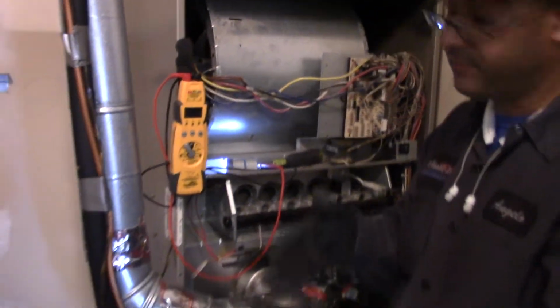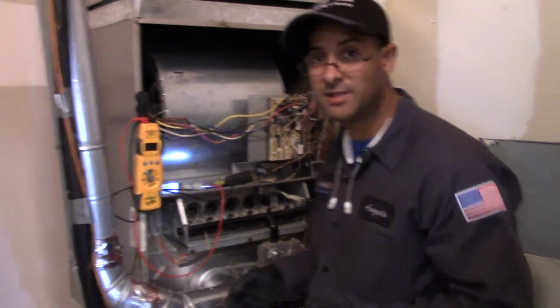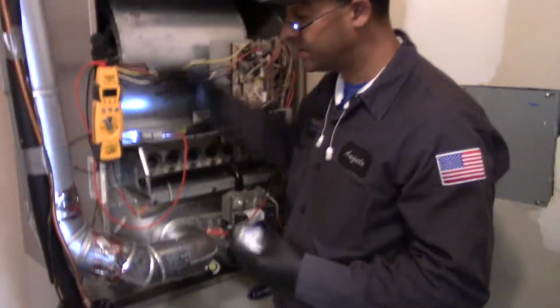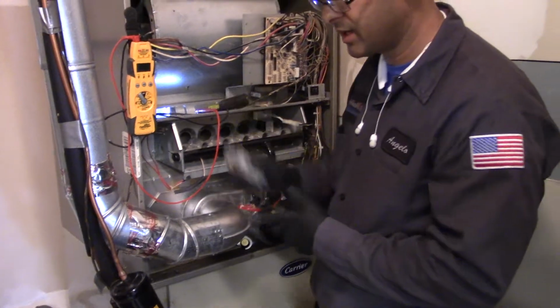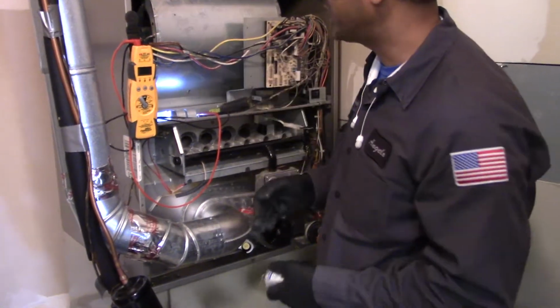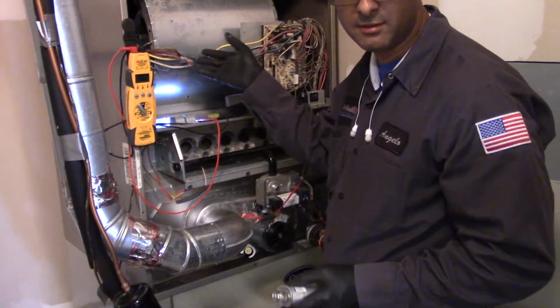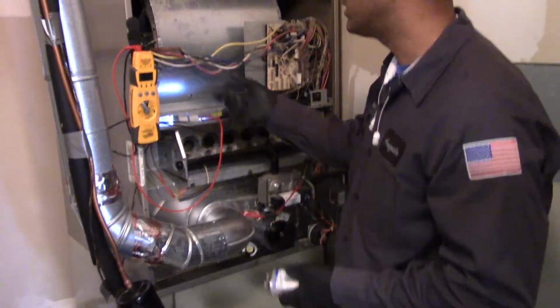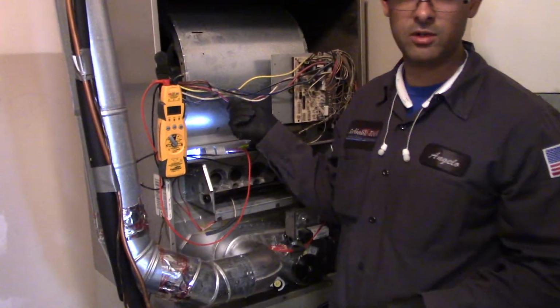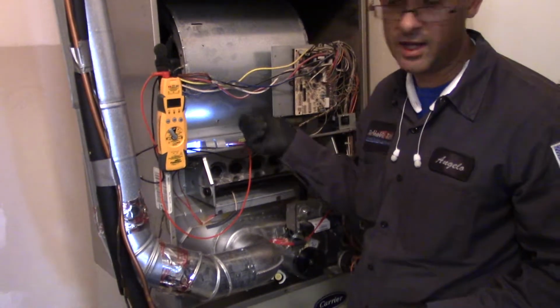Now, if the motor is bad—if I put a new capacitor in and that motor was overheated, and I checked the capacitor and got 9.2—if I put a new capacitor and the motor turns on after it cools off and it's working, then I'm going to want to do an amp draw on the motor and make sure it's not over-amping and overheating again.